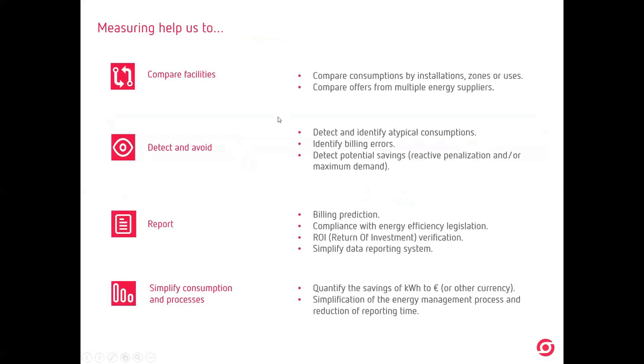Well, measuring helps us to do something. Okay, measuring is helping us to compare facilities. So when we install power analyzers or meters and we connect them through EMS software, this will help us to compare consumption by installations, zones, or uses. So it means that we will know which consumption we have in zone 1, zone 2, zone 3, okay, floor 1, floor 2, floor 3, or by uses. It means the consumption in lighting, in climate, in computers, whatever we have, okay. Depending on those consumptions, we will start doing improvements in the zone or in the use that is having the higher consumption.